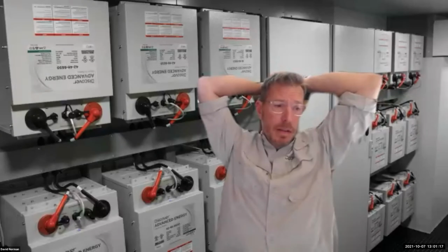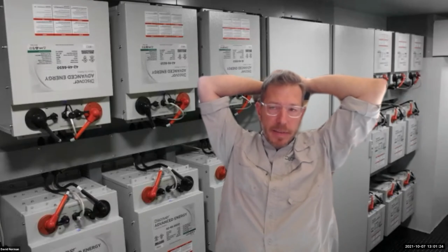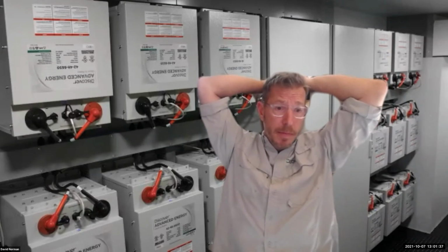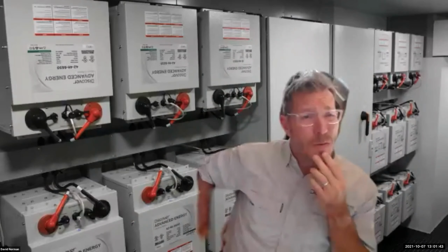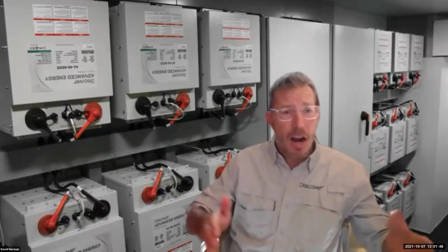It configures itself. In the times that we've reviewed support calls, the biggest thing for anybody who's coming to the world of networked devices is understanding the fundamentals of a CAN network. And that's basically that each end has to be terminated, whether that's through a physical terminator or a terminated port on the end of devices. So, that would be probably the single biggest thing that I've seen from a troubleshooting perspective or a point of failure, particularly with ganging our batteries together.